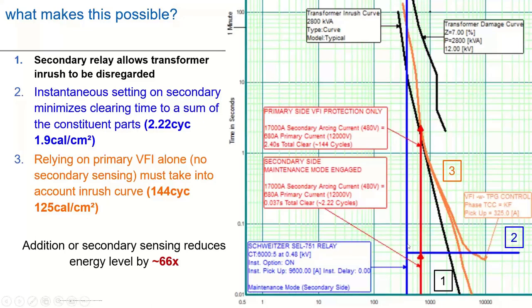And then as we look at our instantaneous line in the 50 setting that we had, we're extremely, extremely low in comparison. So we're at about 2.22 cycles and about 1.9 calories per centimeter squared. And I mentioned before, if we had that 50-51 setting and used something like an ANSI extreme inverse curve, you can imagine this would curve in a little bit more like that. And instead of, say, this 2.22 cycles, we'd be a little bit higher just because of the time delay on a curve like that. But we're still going to be, in the very, very short range, under that 8 calorie per centimeter squared, still within that level two with gloves and face shield, just by having that secondary set of CTs and that extra relaying. That's going to go a huge long way in terms of protection on that transformer.